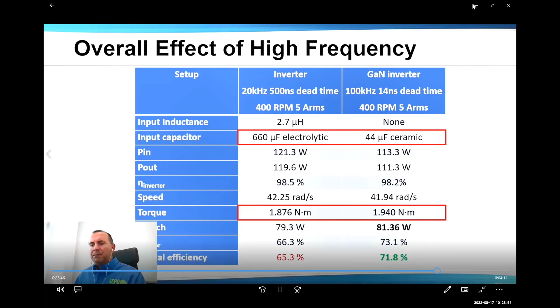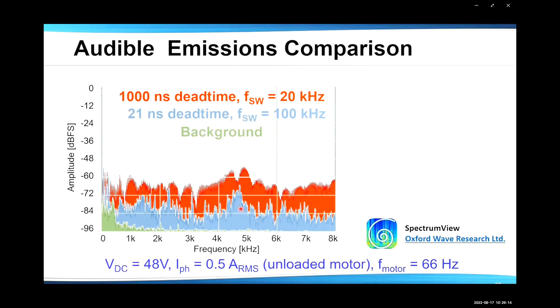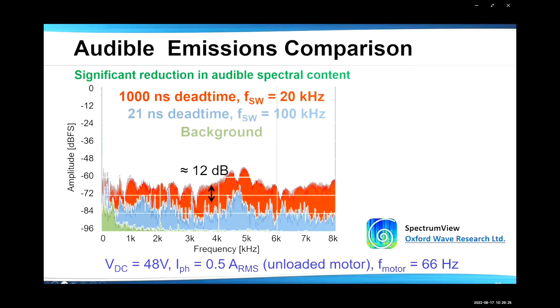Then, proceeding to the next slide, you see that there's another important thing related to the dead time: you may really trigger some resonances in the system and create some noise, and reducing the dead time is going to reduce these resonances and definitely reduce the acoustical noise. And this is an exaggerated example because it's 1 microsecond, and usually in those types of motors that is never used, but it gives you the idea.